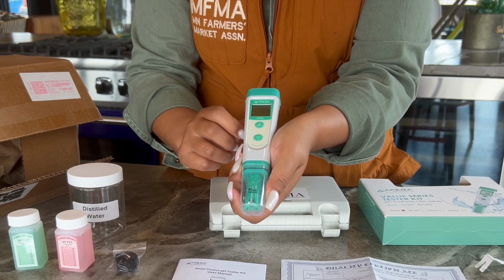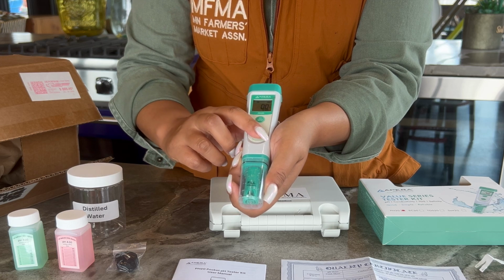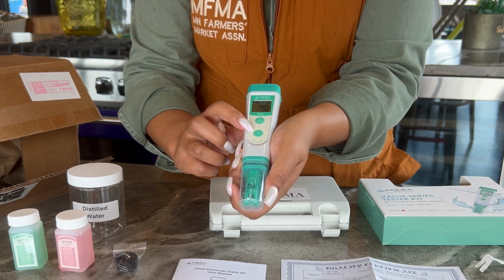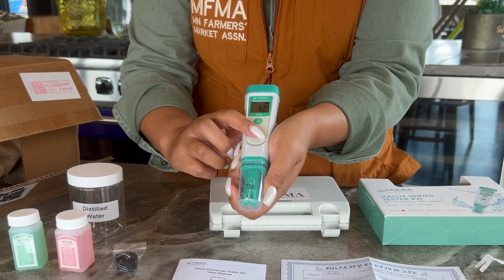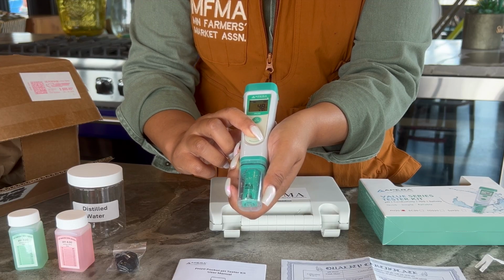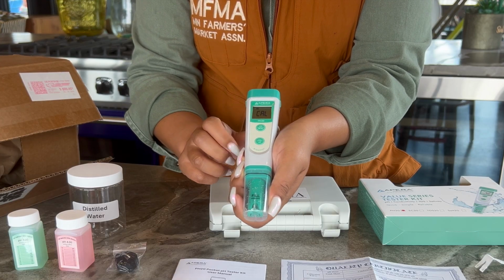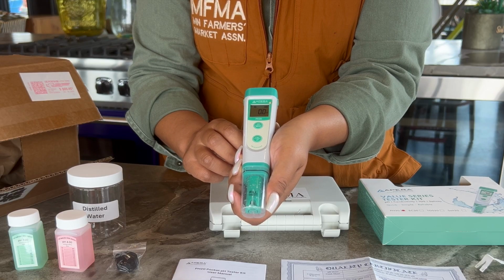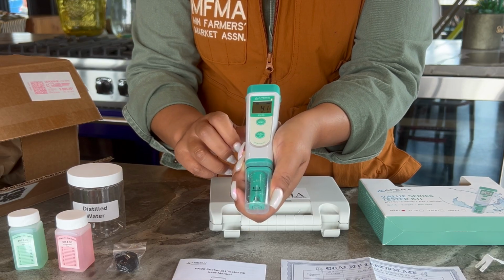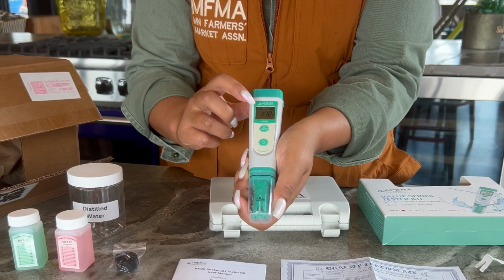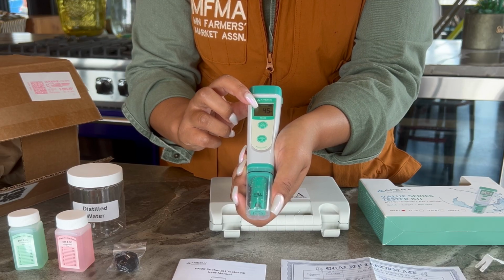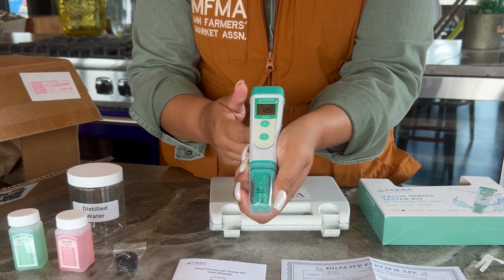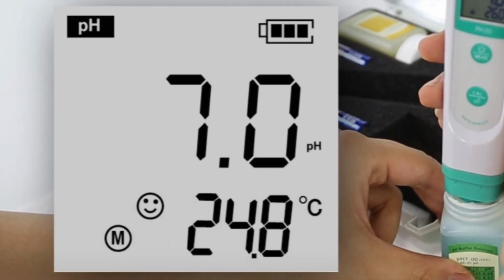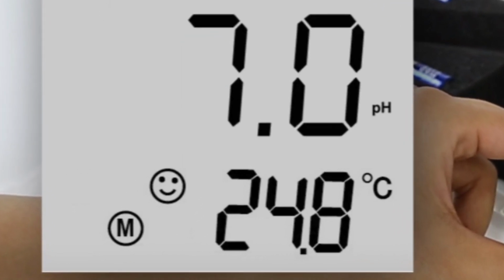A cal button that is used to calibrate the meter using the two calibration buffer solutions. Long press for at least 2 seconds to enter calibration mode. Short press to finish the calibration once the calibration is stable. On this meter, a smiley face appears on the display screen once the reading is stable.